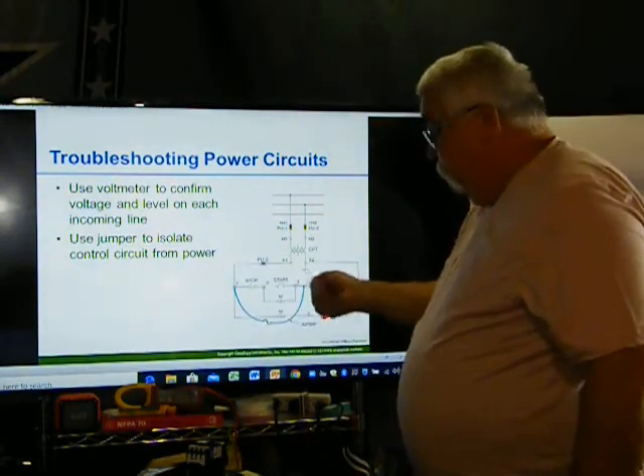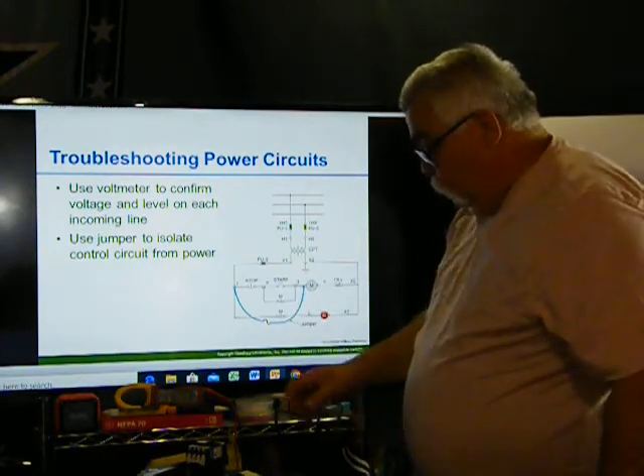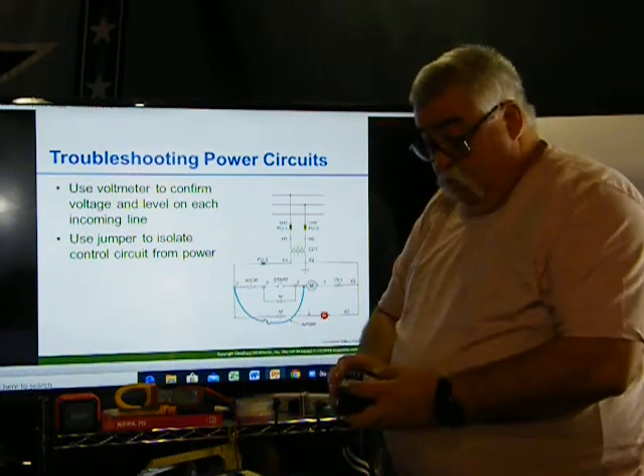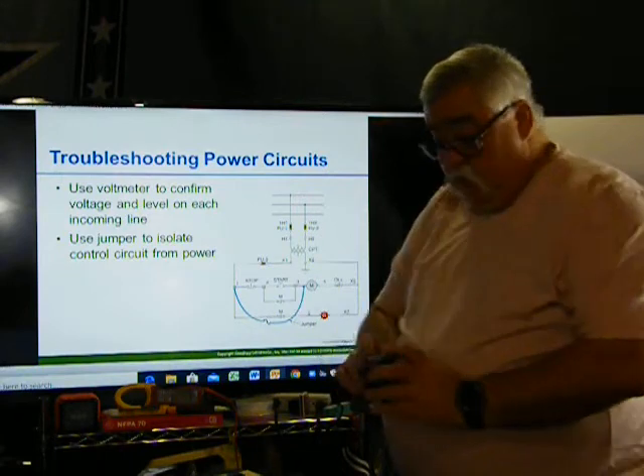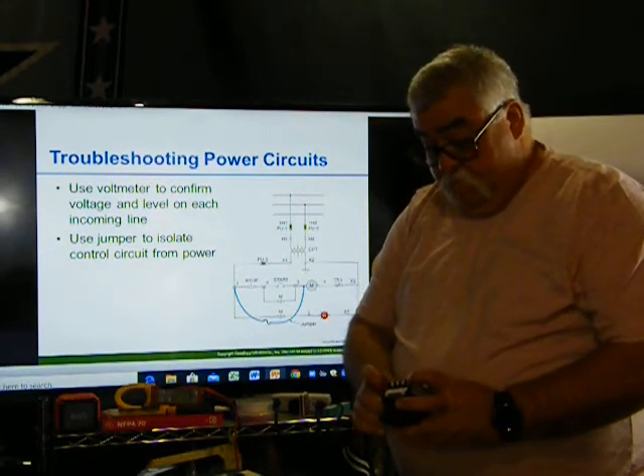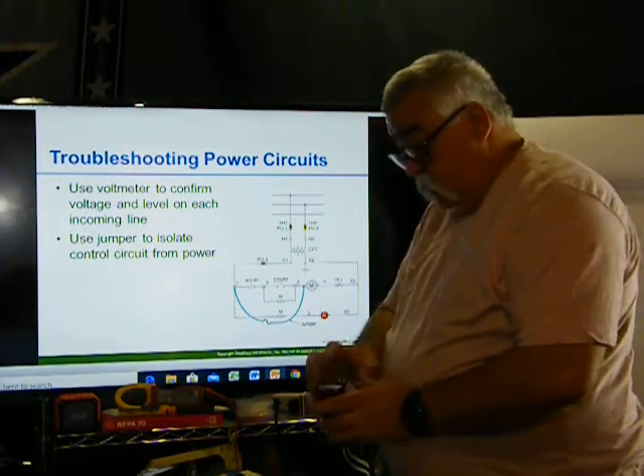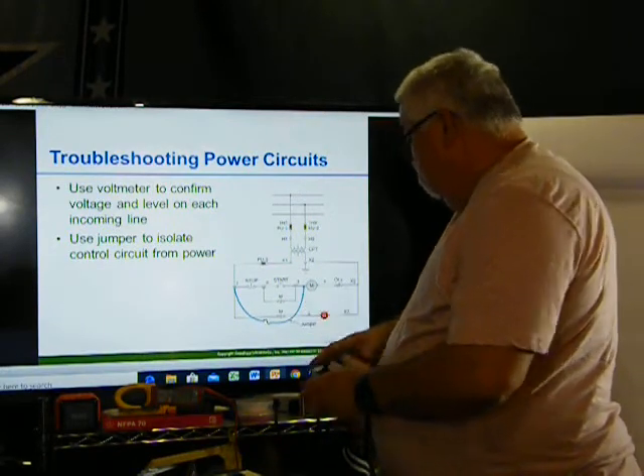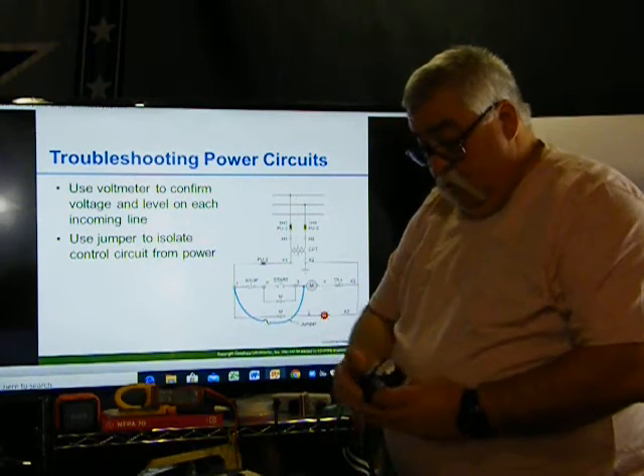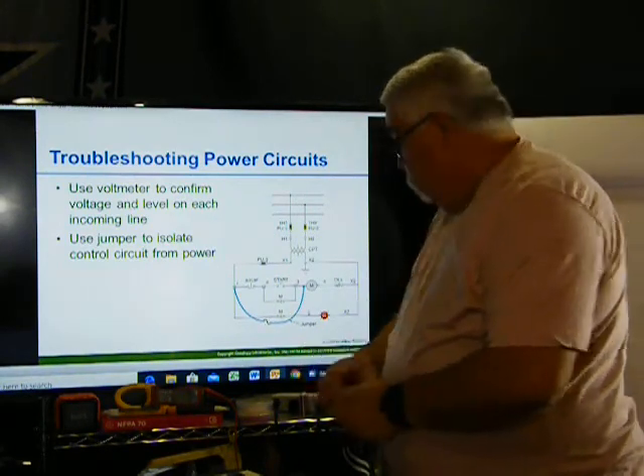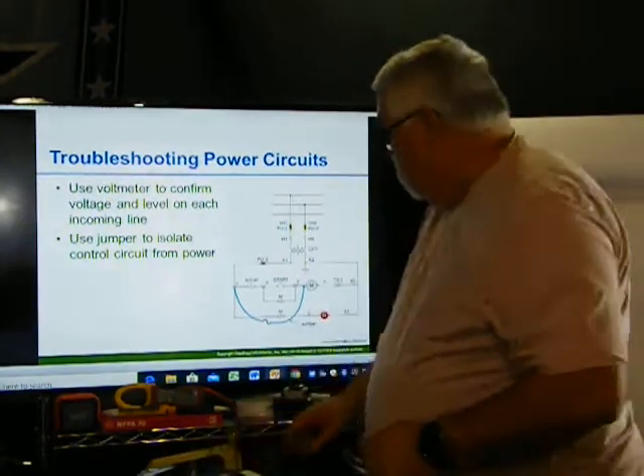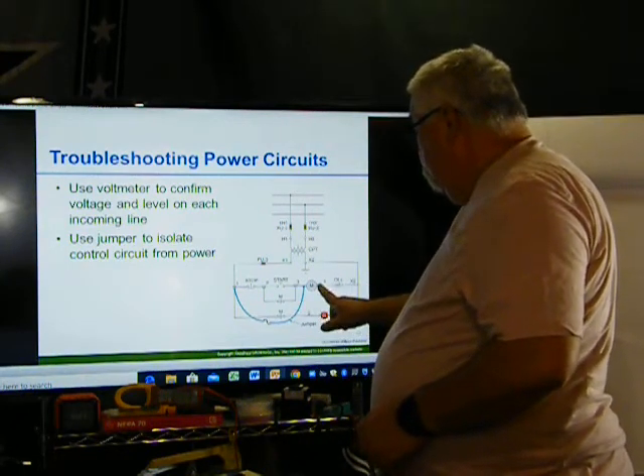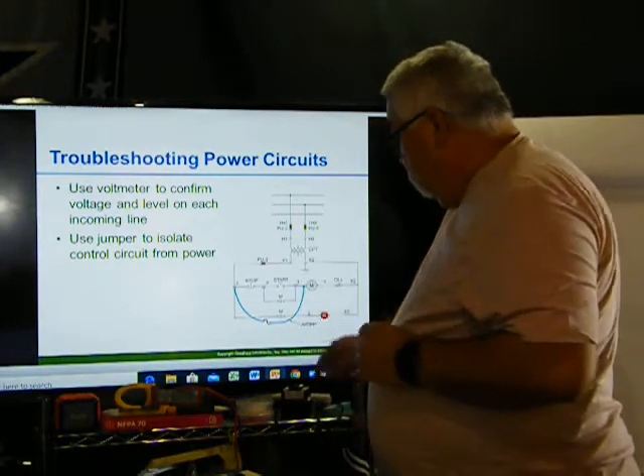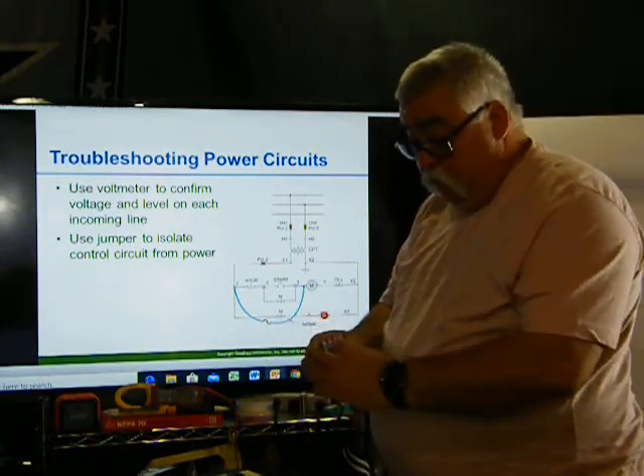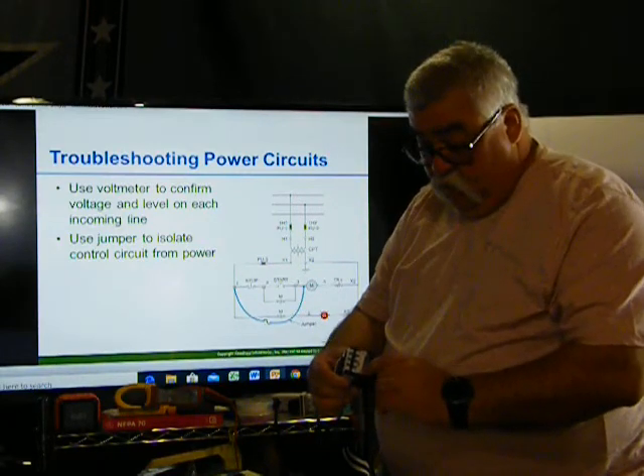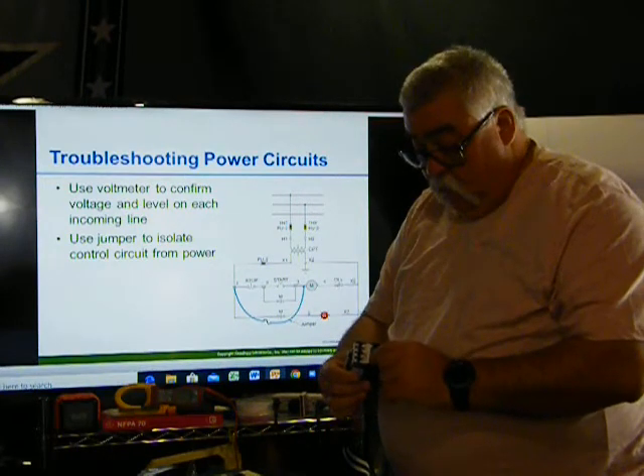Okay, so they're just going straight to here, or you can push it in with a screwdriver. So you just put a jumper, and in this one, a jumper would go from my number 1 where the line is, and then I want to go to the A2. So I want to go from L1 to A2 here on this one, and then that will turn it on because it bypasses here. Okay. Here's number 3, here's number 4, and here is the A2. On this one here, A1 would be here, A2 would be here on my contactor. So from the L1 I would go straight to the A2, and then right down here it's got A1, A2. A1 is my neutral or my other hot, and A2 would be my hot.